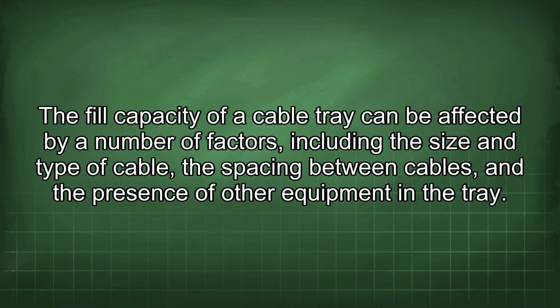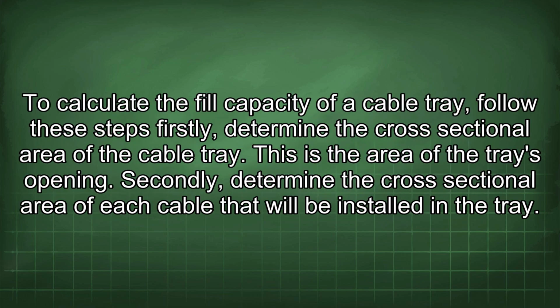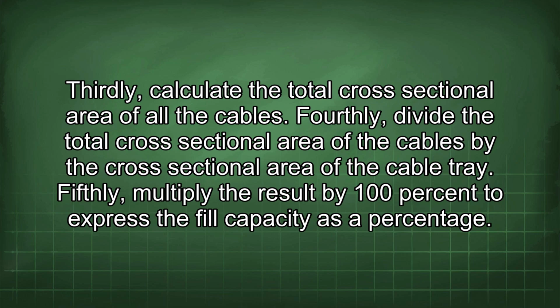The fill capacity of a cable tray can be affected by a number of factors, including the size and type of cable, the spacing between cables, and the presence of other equipment in the tray. To calculate the fill capacity of a cable tray, follow these steps. Firstly, determine the cross-sectional area of the cable tray. This is the area of the tray's opening. Secondly, determine the cross-sectional area of each cable that will be installed in the tray. Thirdly, calculate the total cross-sectional area of all the cables. Fourthly, divide the total cross-sectional area of the cables by the cross-sectional area of the cable tray. Fifthly, multiply the result by 100% to express the fill capacity as a percentage.